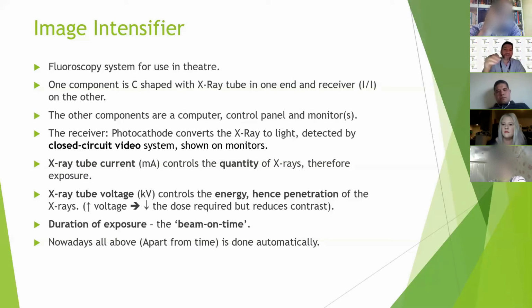And even this is not one radiation; it's a continuous radiation. The machine nowadays controls everything for you, so you get an automated calibration of the current and voltage depending on what the computer in the C-arm thinks is best to show you the image. That's why you don't have to adjust it every now and then, but you still have the ability to do so should you feel that you need to, for example, if there is metal in the way and you want to see the images better.